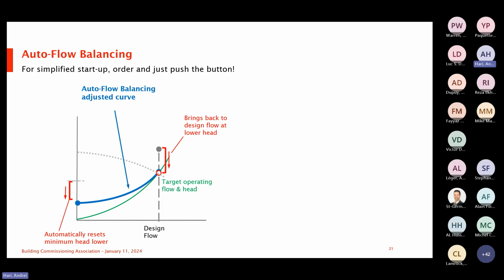or that's what differentiates this type of strategy or this type of logic from traditional, where, when you have that DP sensor in the system, I always come back to it's fixed. Now, if you have a more complex system and you have multiple DP sensors, you are always controlling to the DP sensor with the greatest offset from set point. But then the challenge is that you're over-pumping the other zones as well. So what this affords us, and this starts getting into other technology, incorporating pressure independent control valves, is that we can always optimize the pumping energy based on what the system requires in the application at that point.